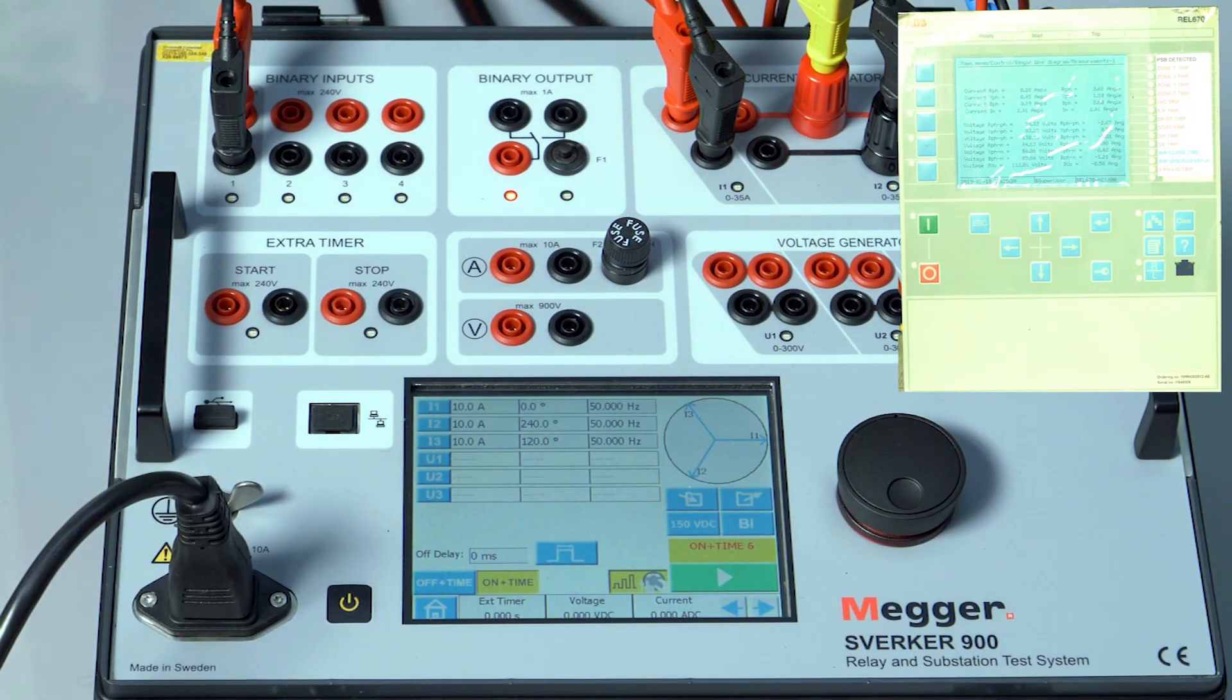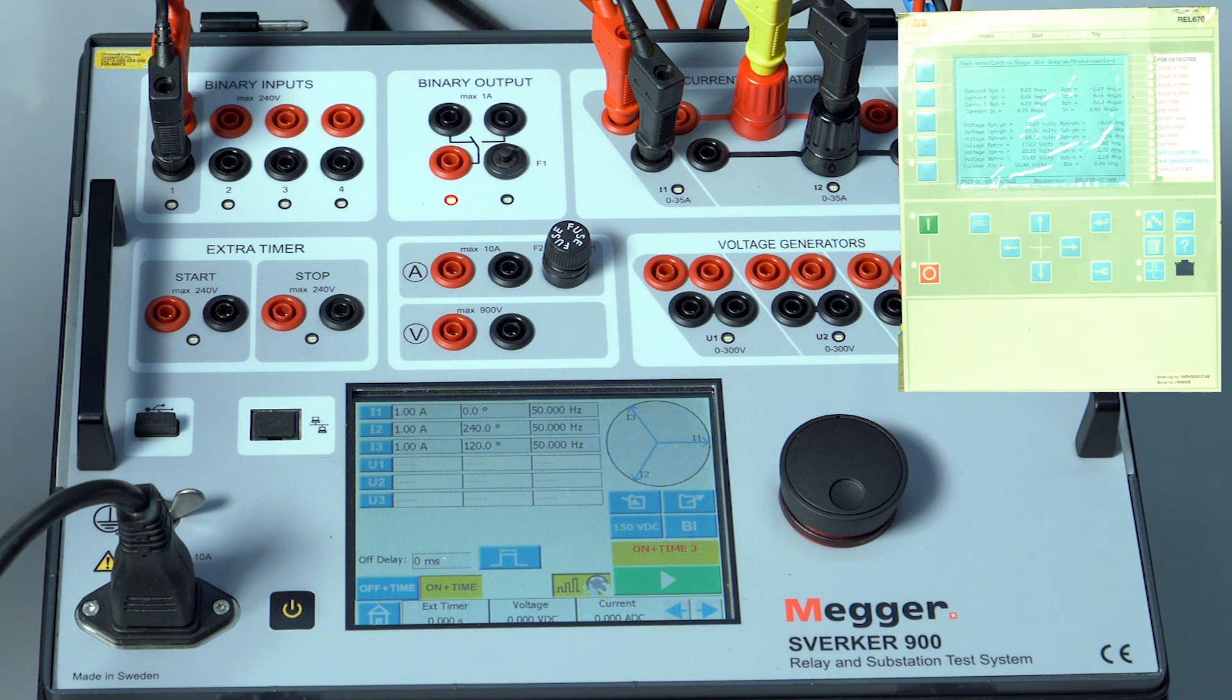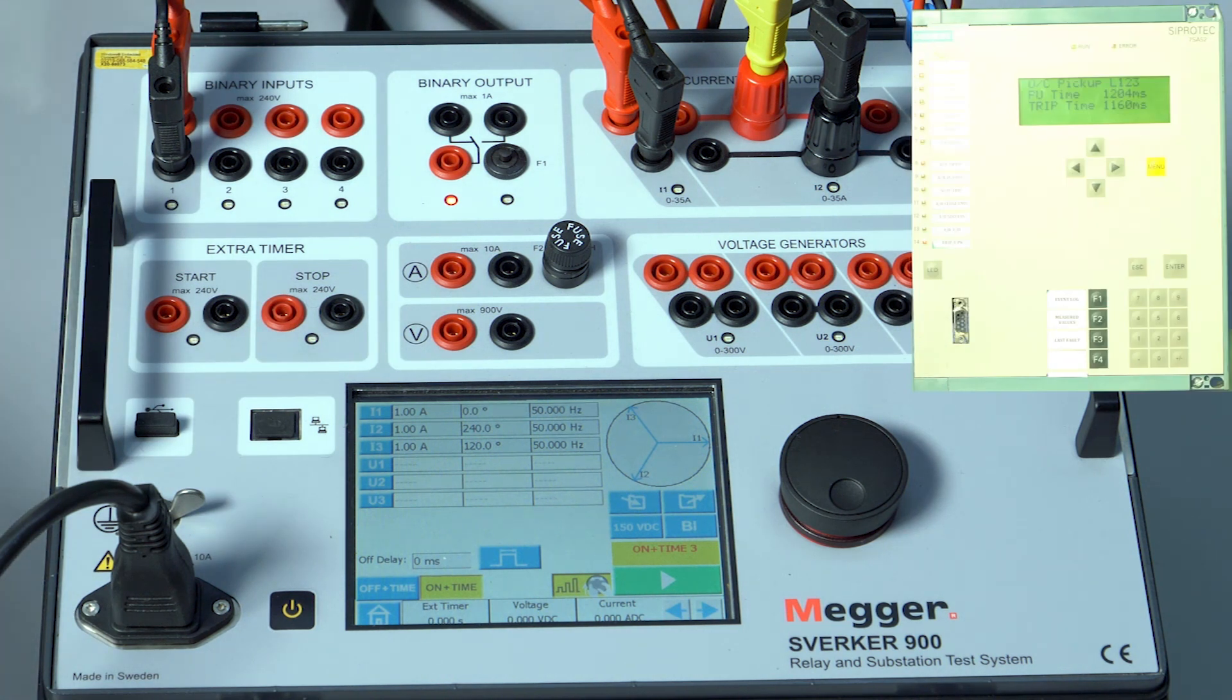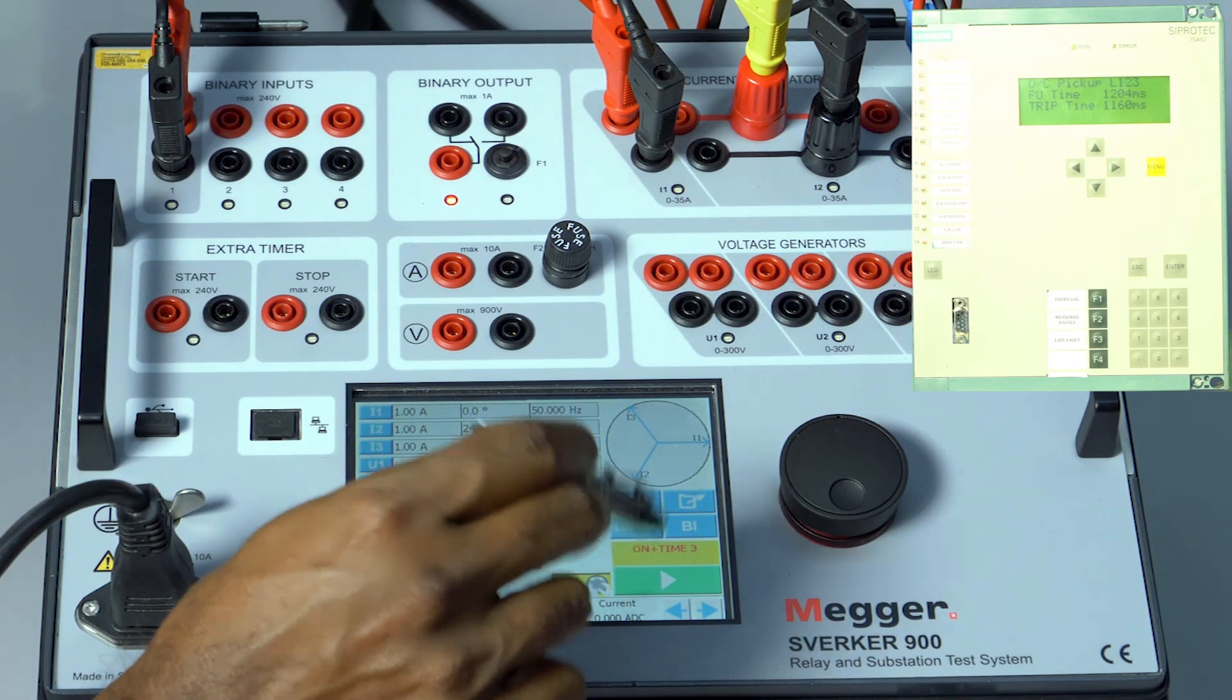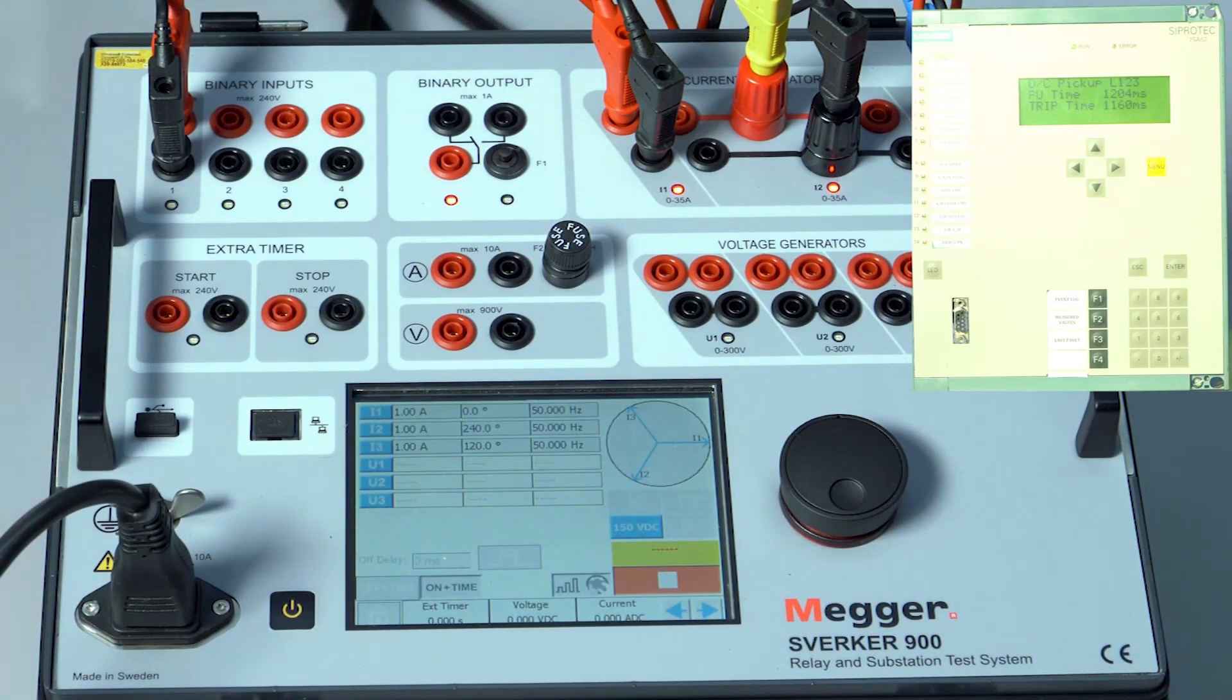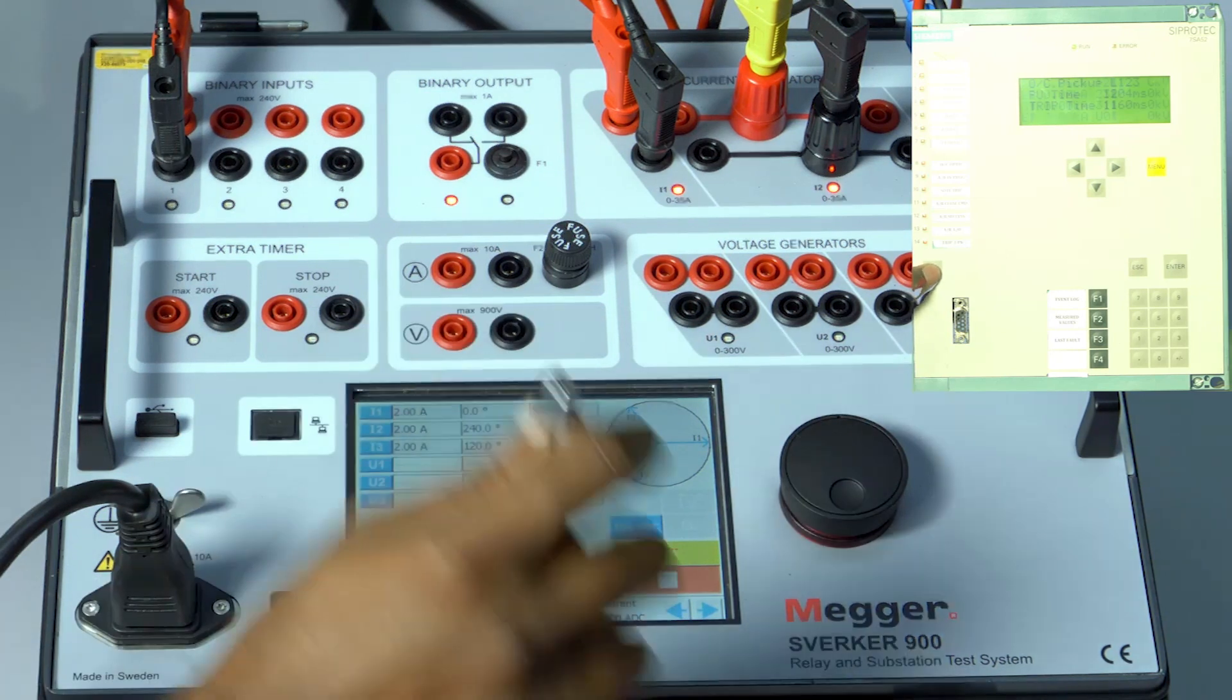IDMT automatic plotting multiple timing test curve ABB and Siemens relays part two. Now let us test the Siemens relay. IDMT curve is enabled in Siemens relay. Using the same option, I'm going to inject by pressing the play button. Now let me inject two amps in all the phases. Now press the button to inject. The relay has operated in three point nine eight four seconds.